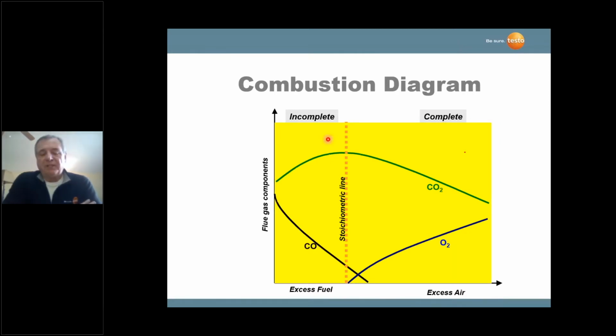Carbon monoxide, another measurement that we measure, very important measurement because carbon monoxide is the toxic gas. It is a dangerous toxic gas, but we minimize it in our combustion process going out the stack. So on the excess fuel side, you'll see that the carbon monoxide crosses over into the excess air side, but it's at low concentrations. As we add more and more air, then we're away from the higher concentrations of carbon monoxide. Now, if we go too far excess air, what happens is that curve of CO comes back up. Reason why is we're cooling down the flame temperature.